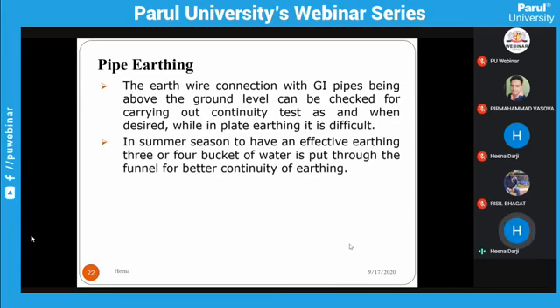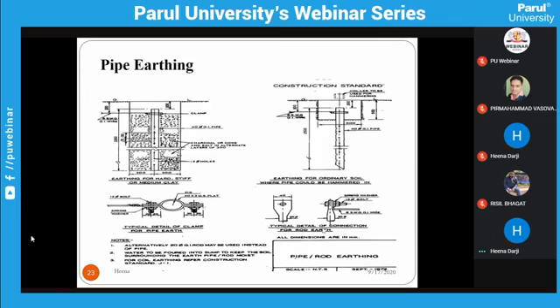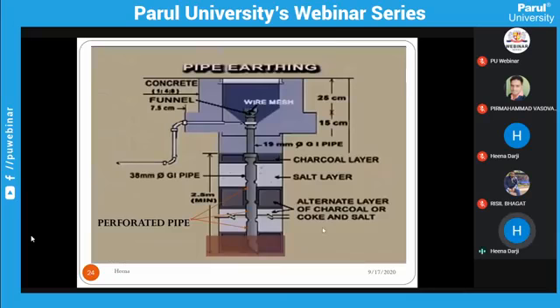In summer seasons, to have effective earthing, 3 or 4 buckets of water are put through the funnel for better continuity of earthing. So you have to maintain your resistivity. So you have to add some water, 3 or 4 buckets, and your resistivity comes down. This is pipe earthing.